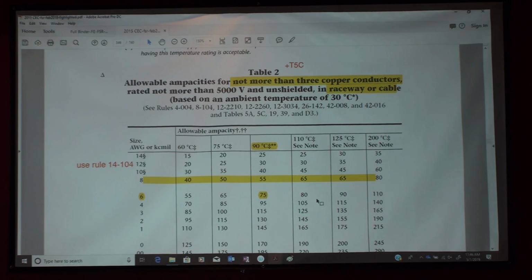What I just did is, imagine you are putting all these wires which are good for 75 amps together in an enclosed area which is a conduit. Every wire is now getting heated up because it is carrying some kind of amps. So because it's an enclosed atmosphere, each cable is not even capable of doing 75 amps anymore. It's able to withstand now 52 because of enclosed area and heat around it. If these 20 cables were outside in free air, you would not use any derating factors. Your answer will still be based on just table 1. No deratings are needed when conductors are up in free air.